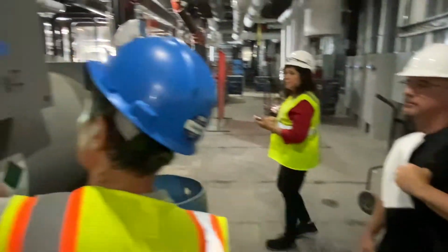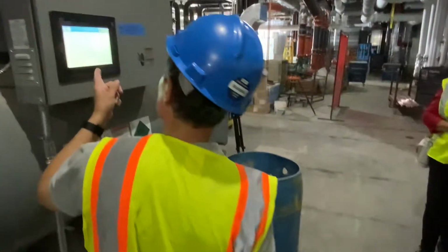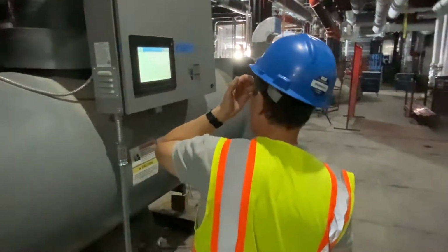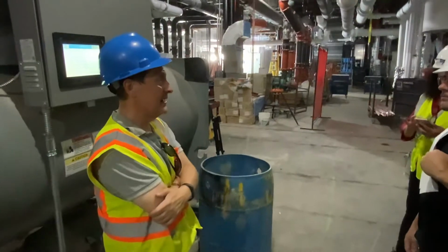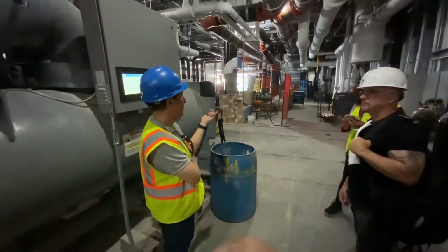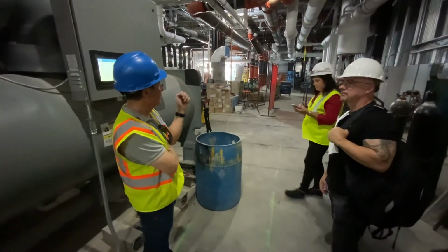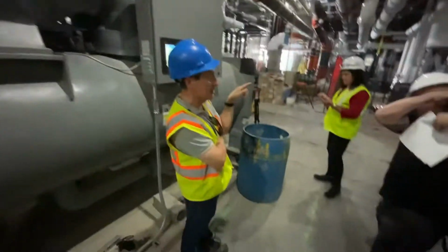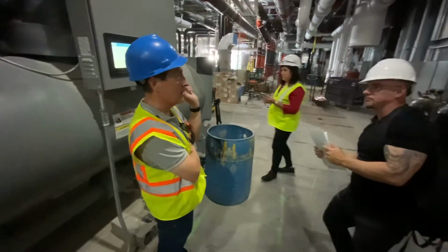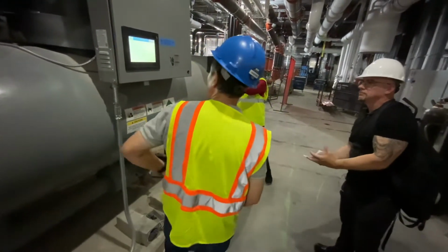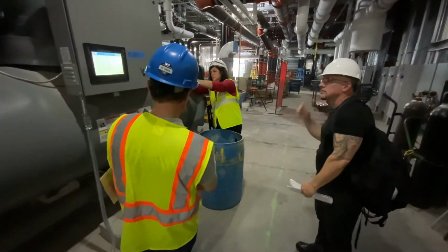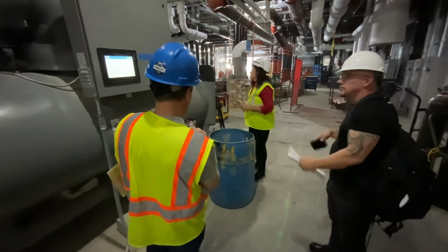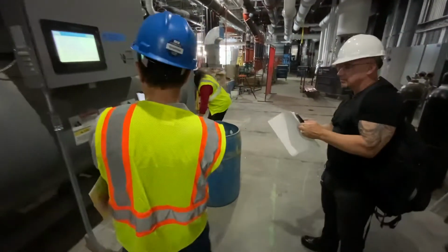High condenser approach. We're doing some kind of head pressure control logic right now, which isn't being done right. It needs to be corrected. We've let them know, but they just haven't gotten around to it. Like I said, there is an output signal that they should follow for controlling the tower water temperature. I'm going to take a picture of this just so I have a record of it. If you want to get a hold of us, just email us.